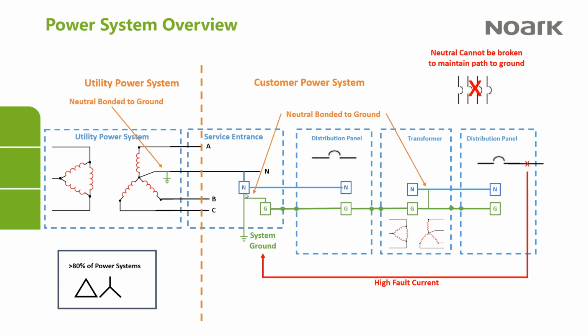So, a quick overview of power systems in North America. I'm going to keep this focused on commercial buildings. I won't venture into residential, and I won't talk too much about industrial. The typical layout of a power system for a small or medium commercial building is that the utility will supply a 3-phase 4-wire system from a Y-connected transformer. That's what you see on the left-hand side here. This is all part of the utility's power system. Utility power systems are not regulated by electrical codes, and they don't even have UL standards for some of the things done there. So this is all outside the purview of the National Electrical Code.